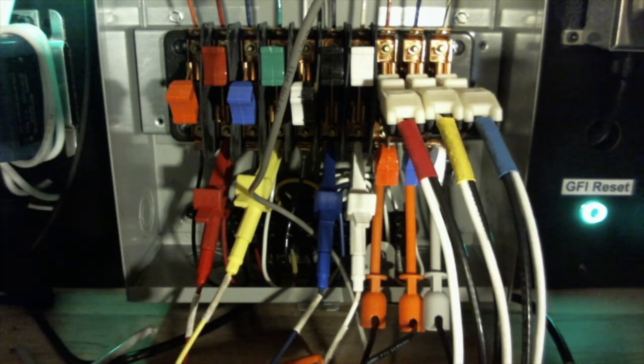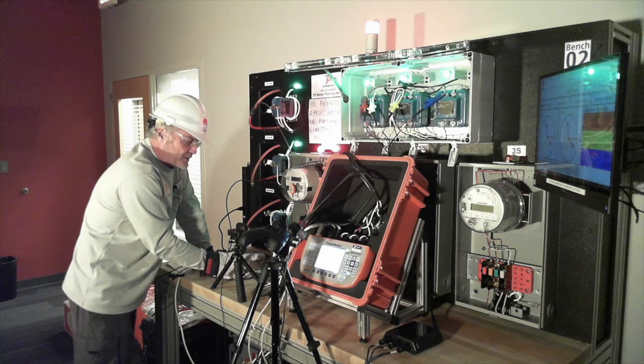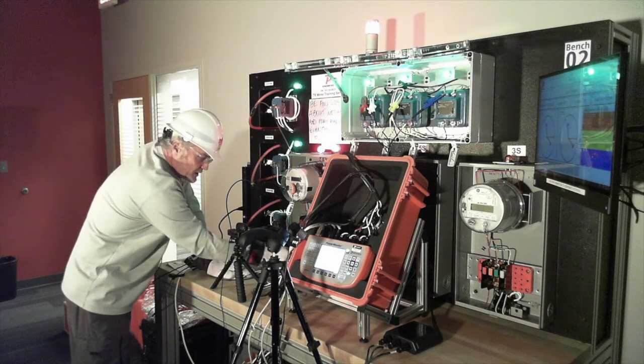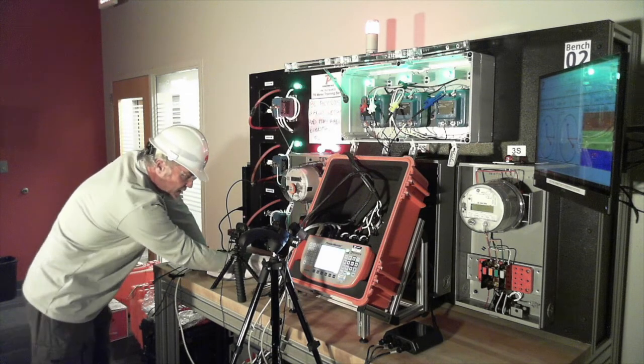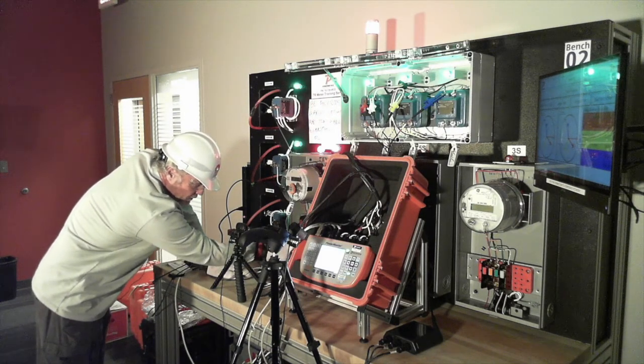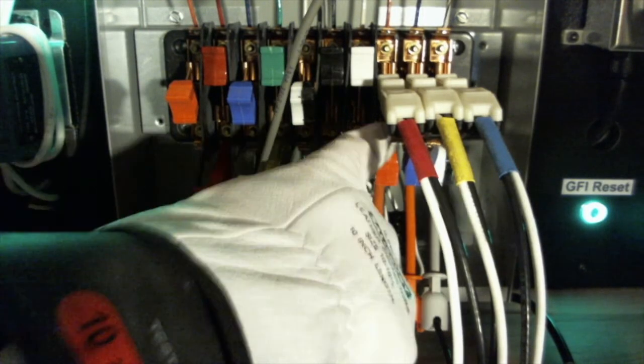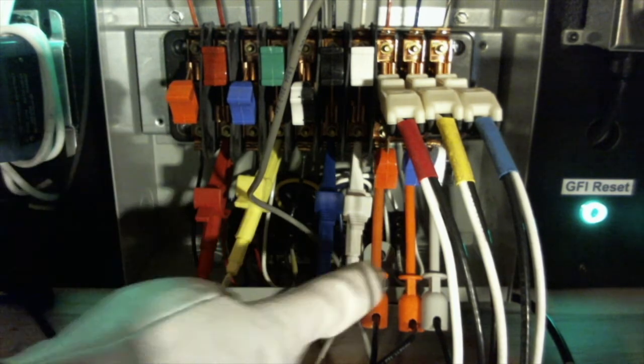So here I left these connected at the bottom. I always make my connection on the phase at the bottom of the return, okay? One way in my pea-brain when I was first doing this that I got in my head to remember, when I was out in the field, just like y'all figuring this out, I said, okay, I've always got to get around that long handle down there to make my connection at the bottom on that phase. I'm always getting around the long handle. I have a long swing handle on the return. I've got a short swing handle on my shunts right here.